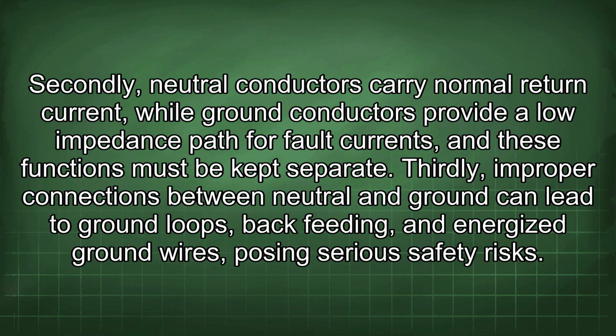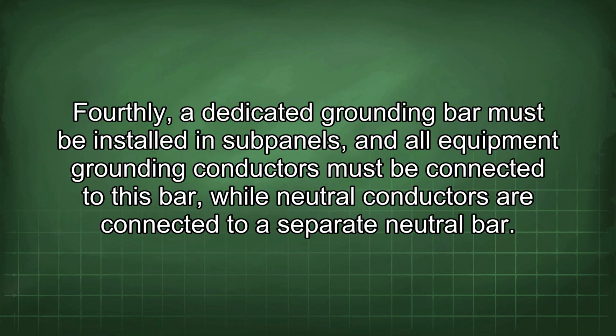Thirdly, improper connections between neutral and ground can lead to ground loops, backfeeding, and energized ground wires, posing serious safety risks. Fourthly, a dedicated grounding bar must be installed in subpanels, and all equipment grounding conductors must be connected to this bar, while neutral conductors are connected to a separate neutral bar.